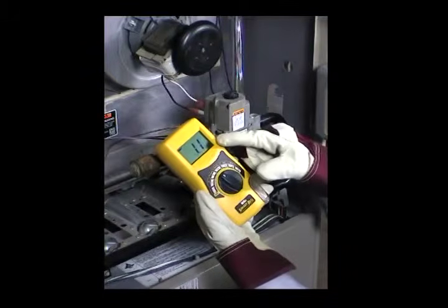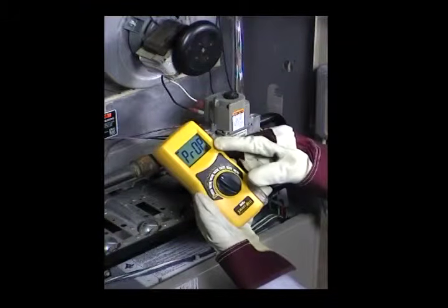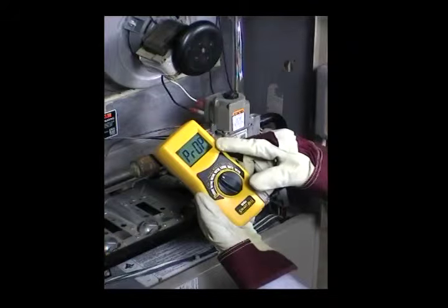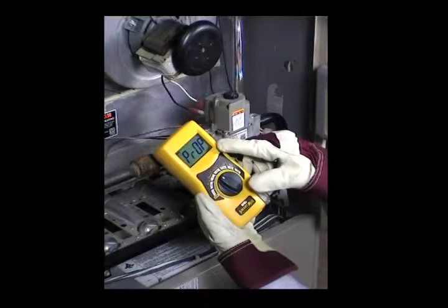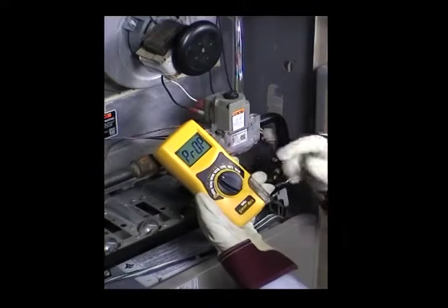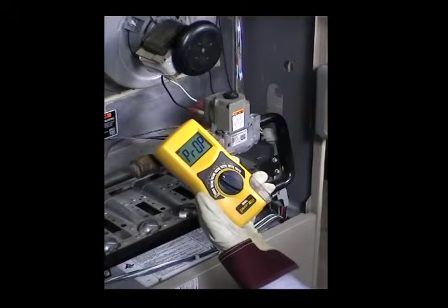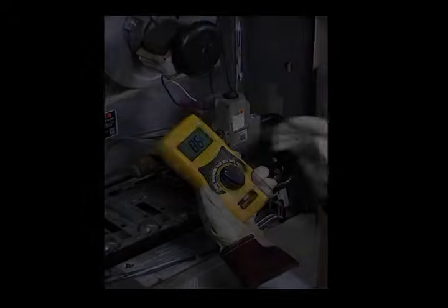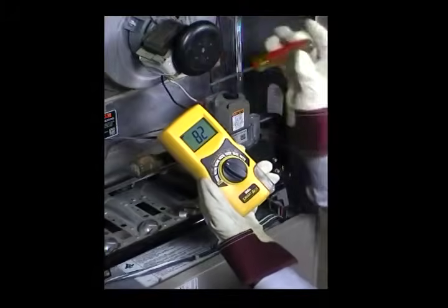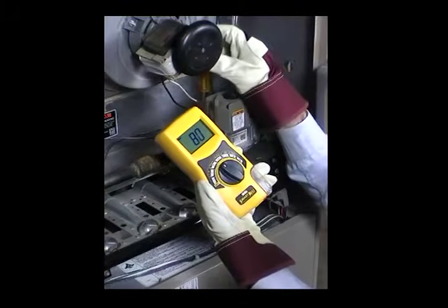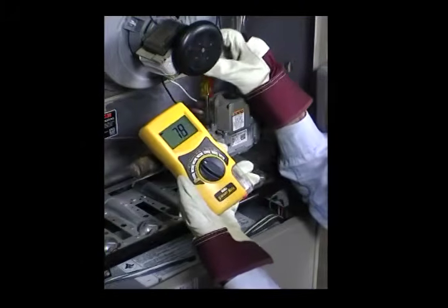And you'll notice that in the display, it'll give you the selected fuel from the last test, and then it'll start flashing to the fuel that you're picking. And then after it's verified that that's the fuel, it'll start a countdown at 99 and go down to 1. And I'm doing this on a gas system, so I'm prepared to make adjustments to the gas pressure as soon as I call for heat.